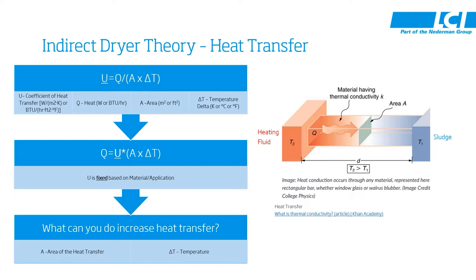Now instead of the thermal conductivity term, we use a coefficient of heat transfer. This is represented by the letter U and equals the heat Q divided by the dryer area times the delta T, or the temperature difference between the two mediums. In order to calculate how much heat we can get into a certain application, we rearrange that equation to say Q equals U, the coefficient of heat transfer, times the area of the dryer times the delta T of the two mediums.